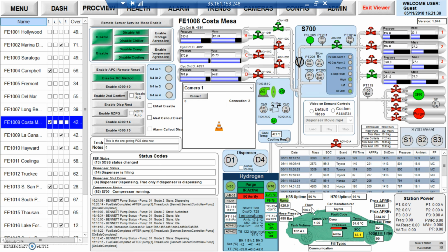So you know how you manually sometimes put in the ramp rate for AOV, the pressure control valve 120? Well, this is what the PLC is asking it to do. So there is a lag, so for the most part it'll be always under the hose pressure, but it's supposed to be actually leading the hose pressure. Okay, so hose pressure is pretty accurate, but the PT124, that one is on a 4 to 5 second timer. It's just the way it is, just because of how we did it. It's slightly slower and lower.